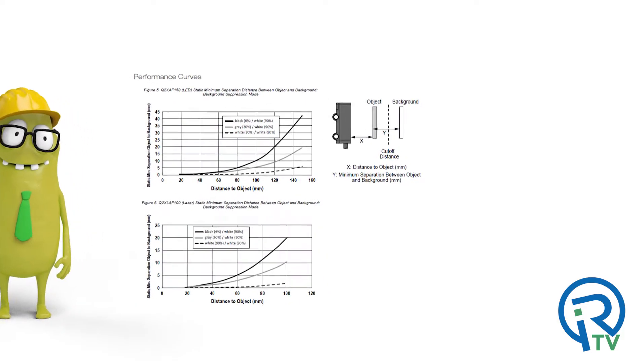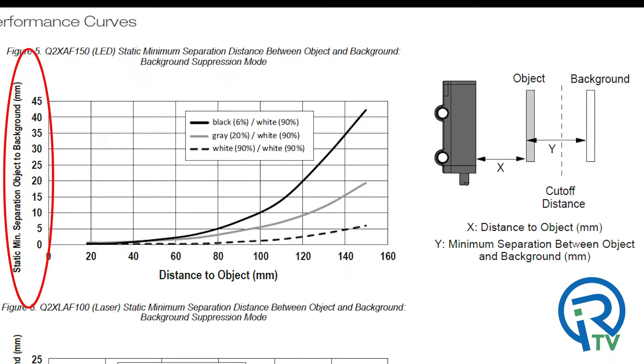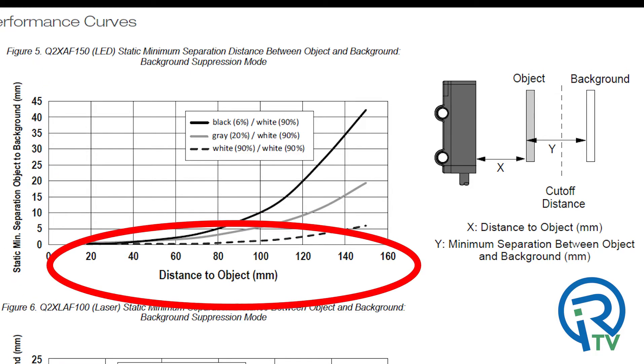These two charts show a static minimum separation distance between object and background. These are really helpful to determine the correct sensor and sensing distance for an application. The values on the Y axis show the separation distance from object to background. The X axis shows the distance of the target.